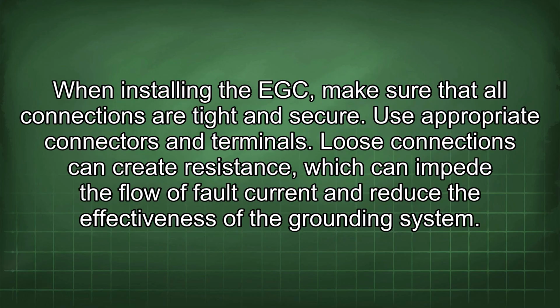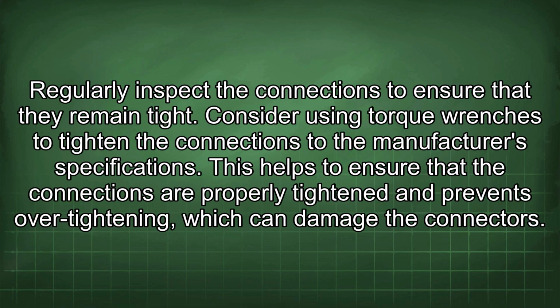When installing the EGC, make sure that all connections are tight and secure. Use appropriate connectors and terminals. Loose connections can create resistance, which can impede the flow of fault current and reduce the effectiveness of the grounding system. Regularly inspect the connections to ensure that they remain tight. Consider using torque wrenches to tighten the connections to the manufacturer's specifications. This helps to ensure that the connections are properly tightened and prevents over-tightening, which can damage the connectors.